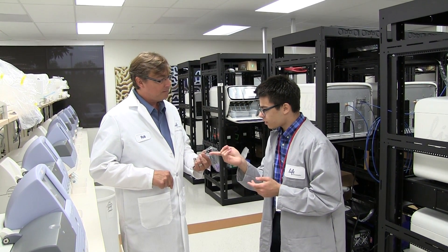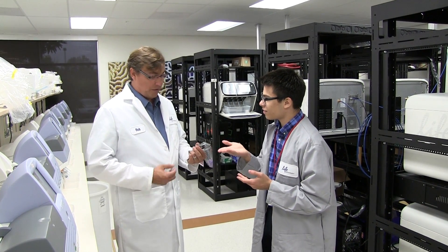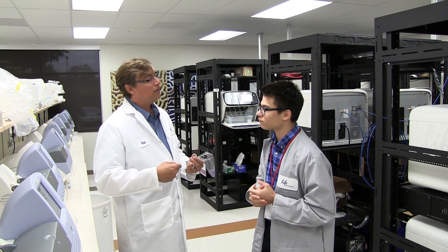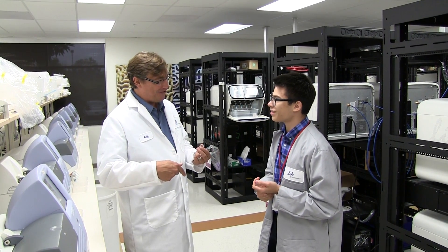The sensors are all underneath each well — you can't really see them here — in what's called an ISFET. That's what detects the pH change, or the change of charge, and that's what we measure.